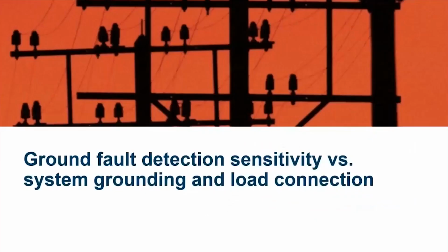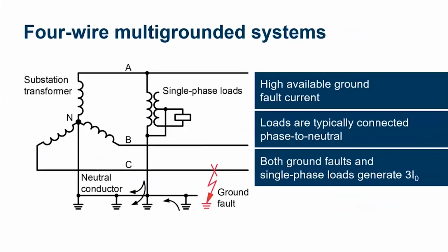Let's talk about power system grounding and how this has an impact on our protection sensitivity when it comes to ground fault detection, and detecting high impedance faults in particular. Most of the distribution systems in North America are going to be 4-wire multi-grounded systems. We have some 3-wire systems and some ungrounded systems, but predominantly we're going to see 4-wire multi-point grounded systems. These systems have high availability of ground fault current because we're solidly grounded. So for faults that are not high impedance faults, that is going to allow us to quickly detect and clear those faults.